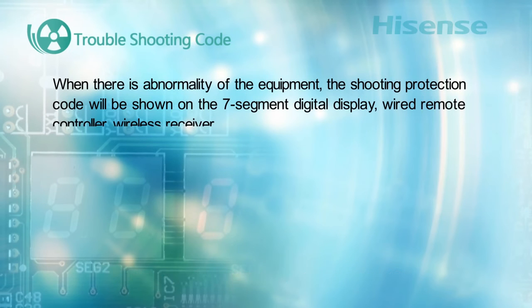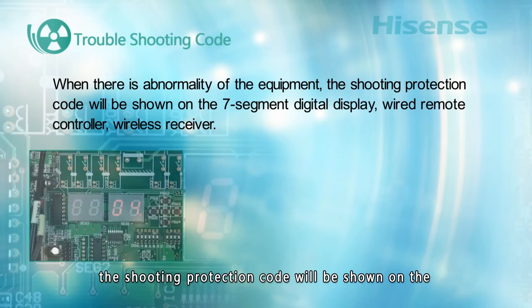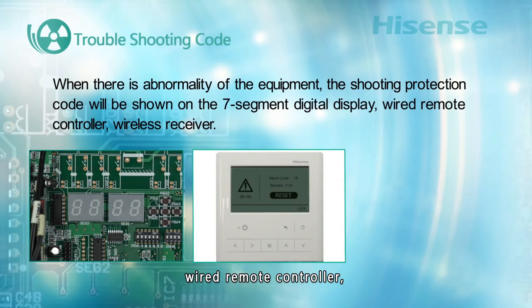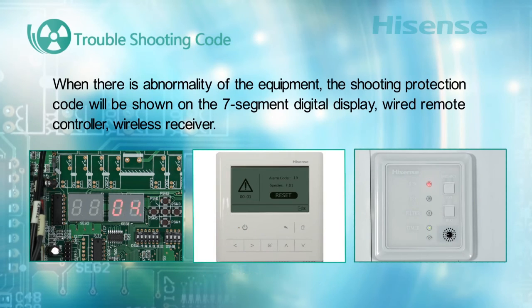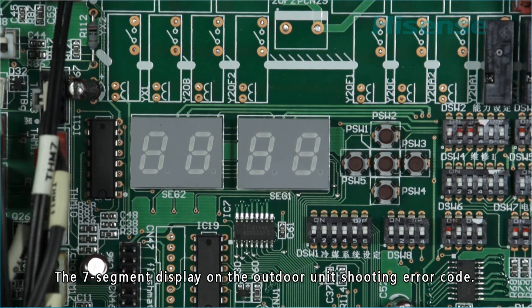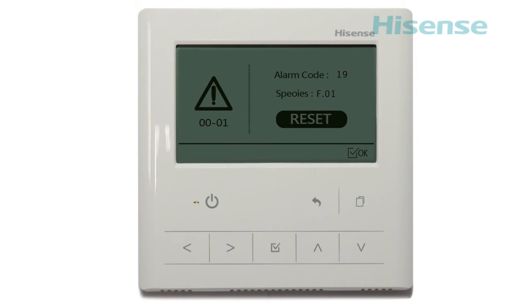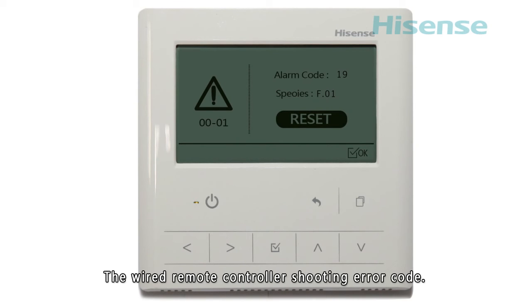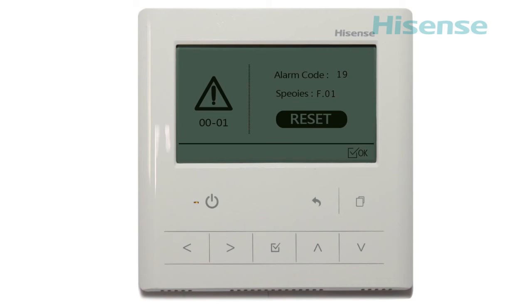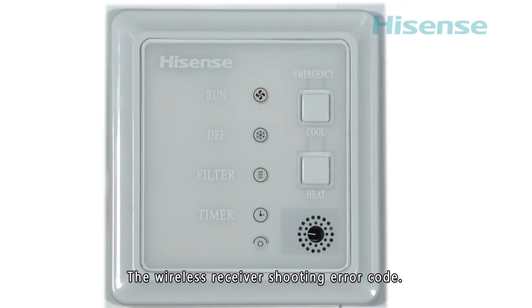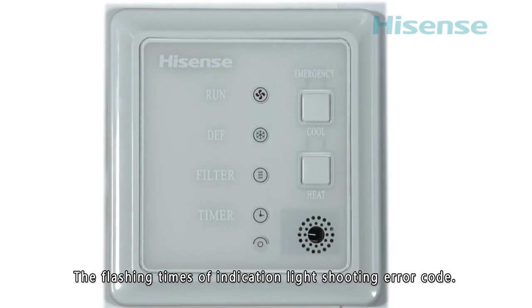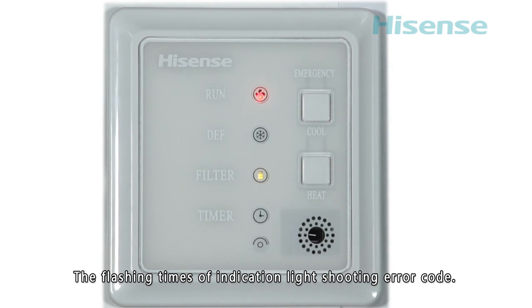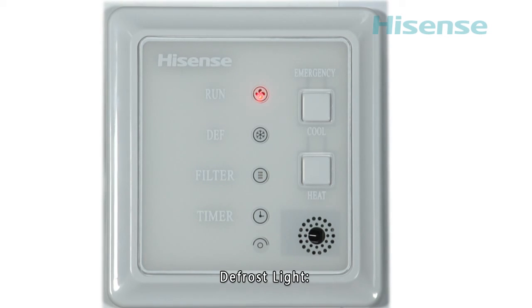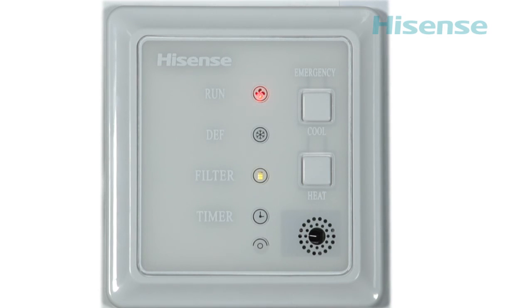Troubleshooting code: when there is an abnormality of the equipment, the troubleshooting code will be shown on the 7-segment digital display, wired remote controller, and wireless receiver. The 7-segment display on the outdoor unit shows the troubleshooting code. The wired remote controller shows the troubleshooting code. The wireless receiver shows the troubleshooting code. The flashing times of the indication lights show the troubleshooting code: defrost light, tens digit; filter light, single digit.